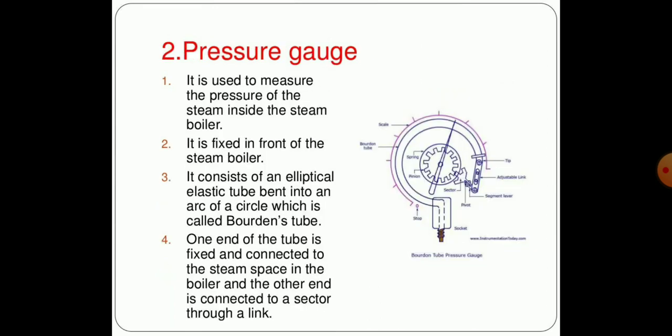The second very important mounting is the pressure gauge. It is used to measure the pressure of steam inside the steam boiler and is fixed in the front of the steam boiler. It consists of an elliptical elastic tube bent into the arc of a circle which is called a Bourdon tube. One end of the tube is fixed and connected to the steam space in the boiler, and the other end is connected to a sector through a link.